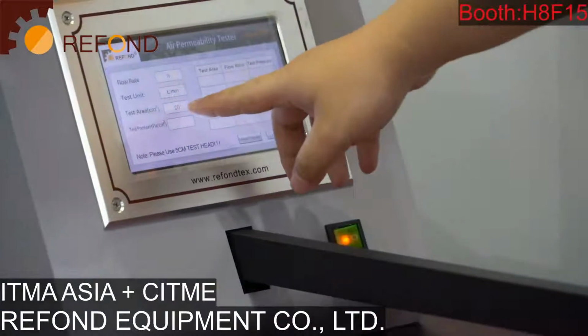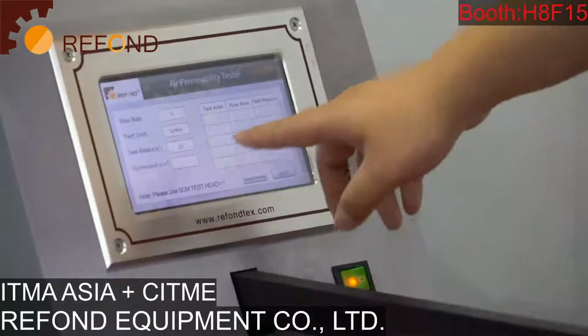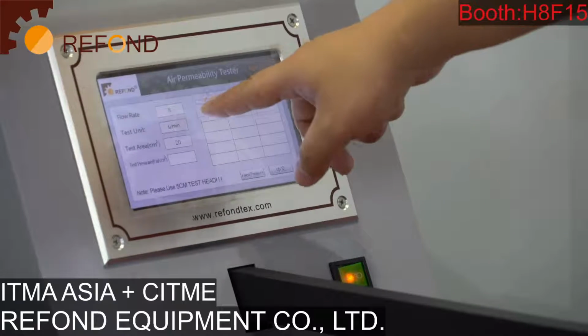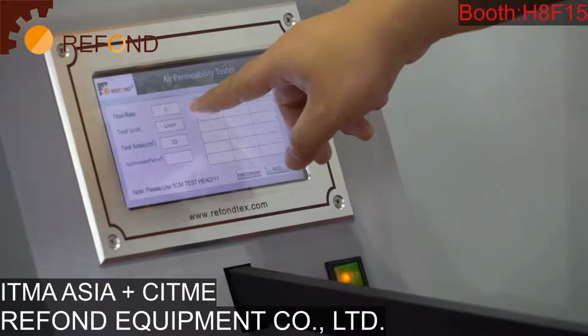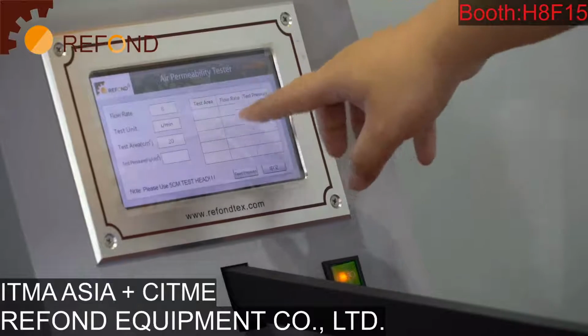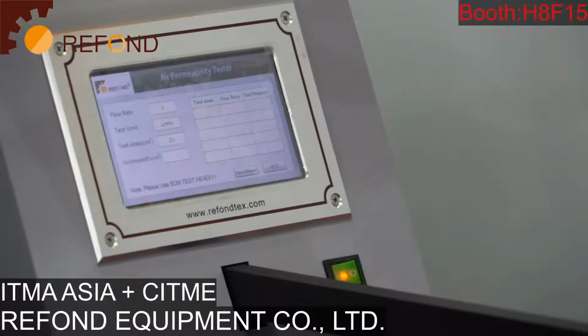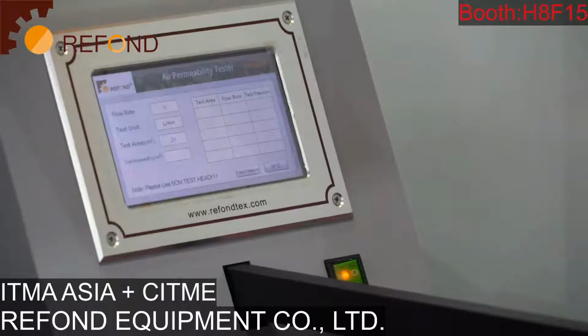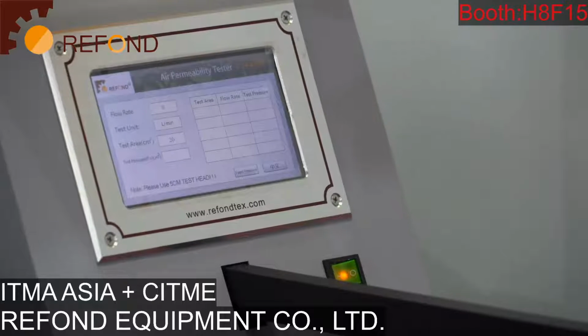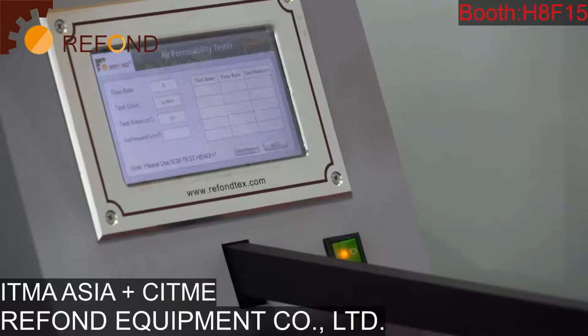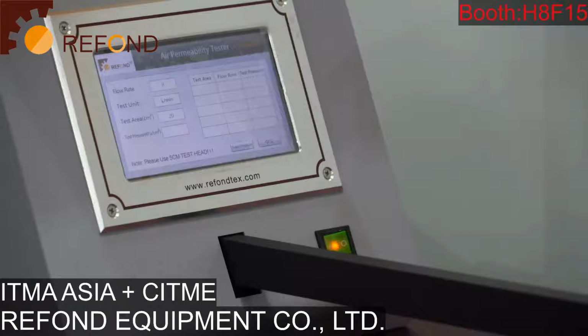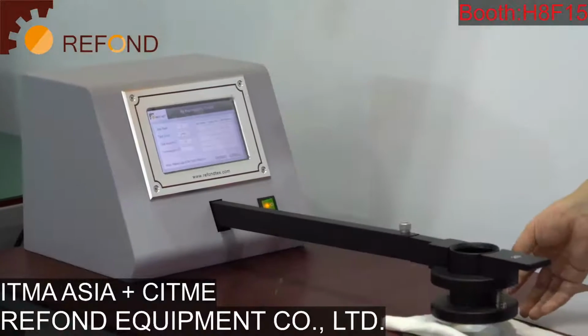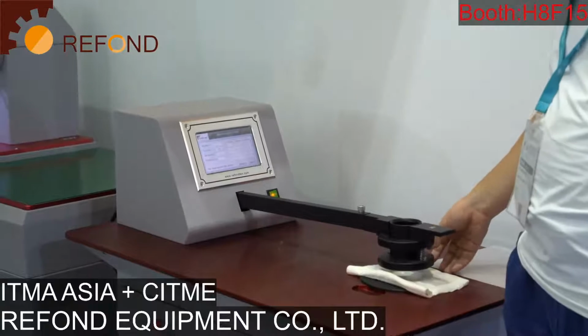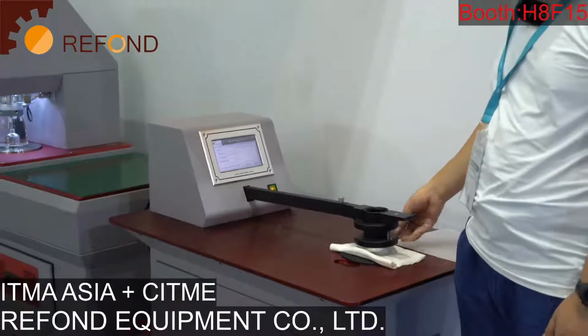For this fixed flow rate test, the standard requires an 8 liters per minute flow rate, and when doing the test, the machine will control the flow rate flowing through the face mask to be 8 liters per minute, and then the pressure across the mask is the main measurement that is required by the test, and it will be used as the result.